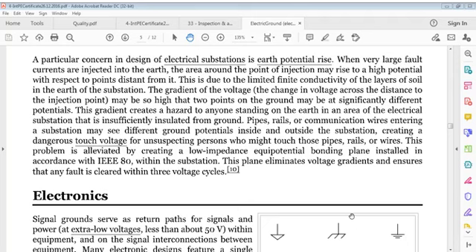A particular concern in the design of electrical substations is earth potential rise. When very large fault currents are injected into earth, the area around the point of injection may rise to a high potential with respect to points distant from it. This is due to the limited finite conductivity of layers of soil in the earth of the substation. The gradient of voltage, a change in voltage across distance to the injection point, may be so high that two points on the ground may be at significantly different potentials.